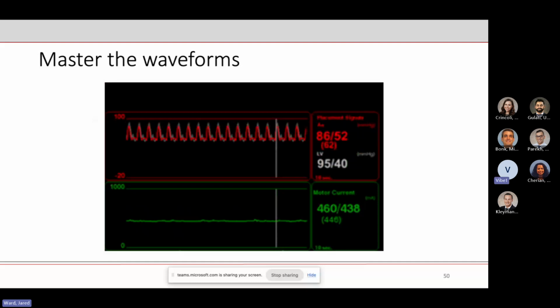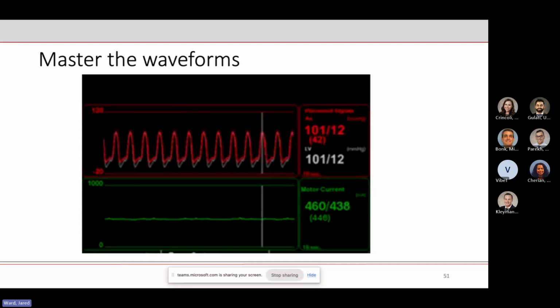And so in this one, your LV waveform looks like your aortic waveform, which is indicative that the Impella isn't in the ventricle at all, right? Both the inlet and outlet valve are just still sitting in the aorta. And then on the next one, the arterial waveform looks like the LV waveform, and that's because it's too deep, right? And so if your motor current is ever flat, you need to say that both of the sensors are on the same side of the aortic valve, whether it's too far out or too far in.